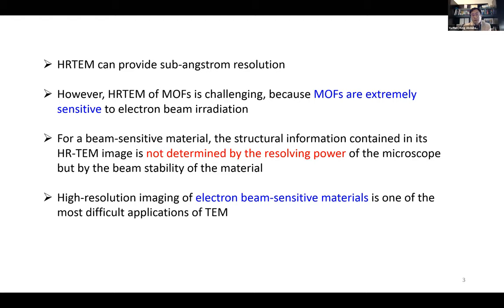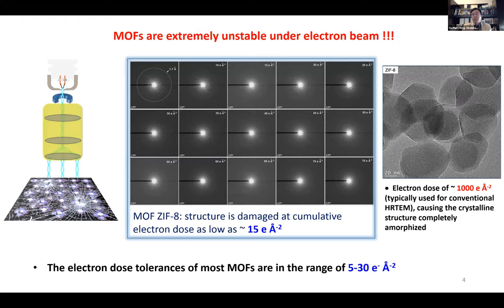The image quality is not determined by the resolving power of the microscope, but instead by the stability of the material — the beam stability. In other words, how much structural integrity can be preserved under the electron beam under the imaging conditions. High-resolution imaging of electron beam sensitive material is one of the most difficult applications of TEM.